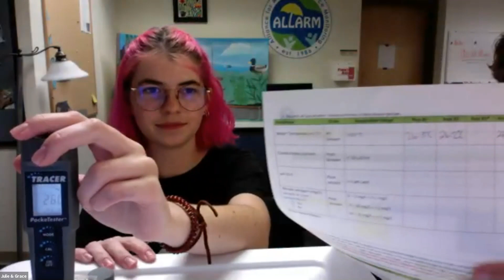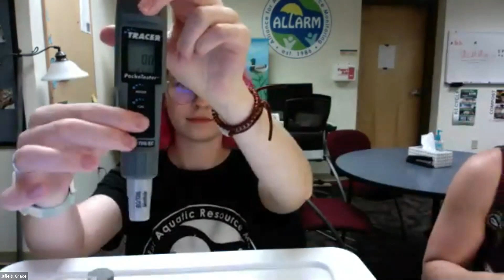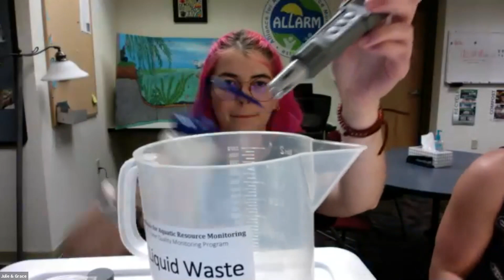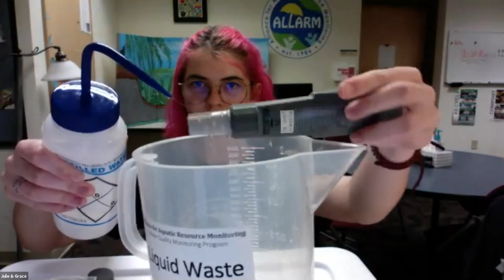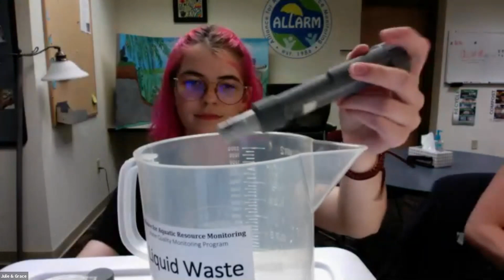Awesome. So once you have your average and your two replicates, if you are in the stream, you would exit the stream, and then you're good to turn your meter off and rinse the electrode with distilled water. As you can see, Grace is taking care to make sure that she gets both sides of the electrode well rinsed with distilled water. And once you are done, you can once again shake it dry.